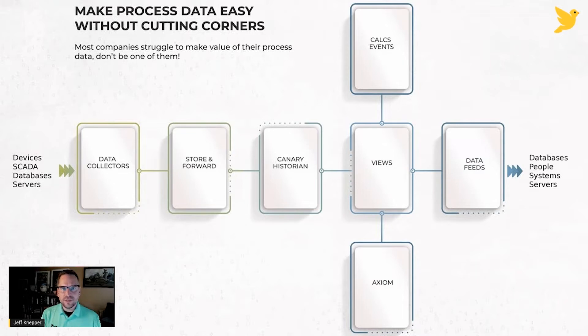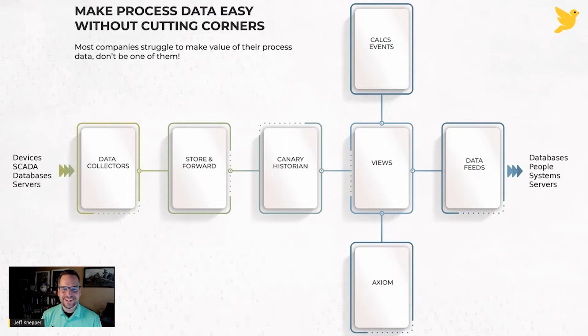Views is the single endpoint for all data access within the Canary historian. If I want to do a trend, I need to connect to Views to access the data inside the historian. If I want to create calculated tags or do event monitoring, I connect through Views. And if I want to publish data to an MQTT broker or create a JSON over WebSocket stream, I need to come through Views to access the data inside the historian.